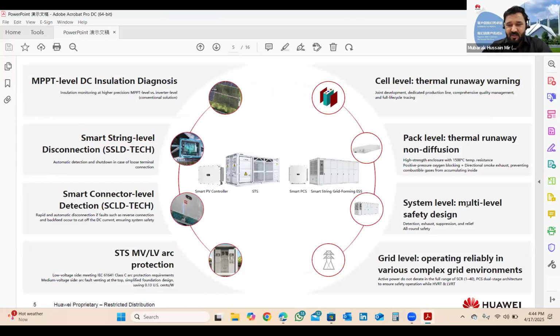Initially, if the participants might remember, there were single MPPT inverters available in the market. Then multiple MPPT inverters started coming into the market. That further reduced the risk of the inverters, and the life of inverters improved a lot. Safety factors improved a little bit more. Now the latest inverters are coming with safety factors at MPPT level. Disconnects are available, sensors are available, diagnostic sensors are available at MPPT level.